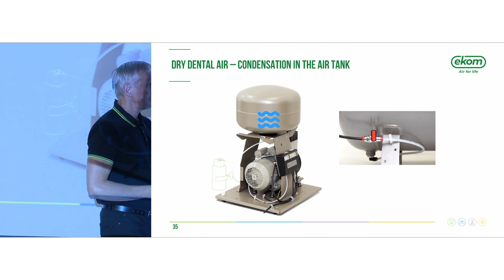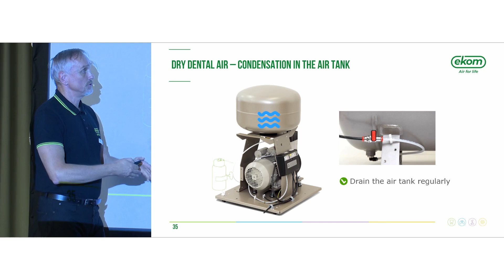It is recommended to drain the tank regularly, of course. This is very important for the nurse or for the doctor, everyone who takes care of a compressor, to drain the tank regularly because of that physics. If somebody doesn't drain the tank regularly, water reduces the air tank volume and the compressor starts and stops more often - it has strange behavior because the volume in the tank is reduced by the water.